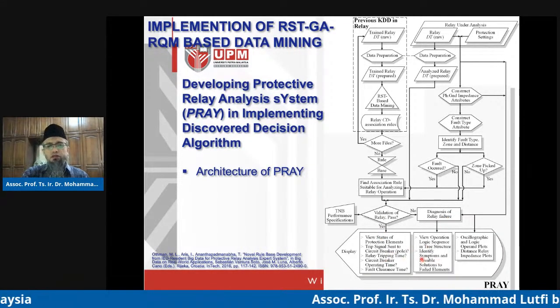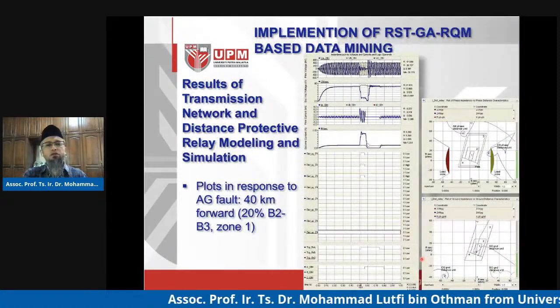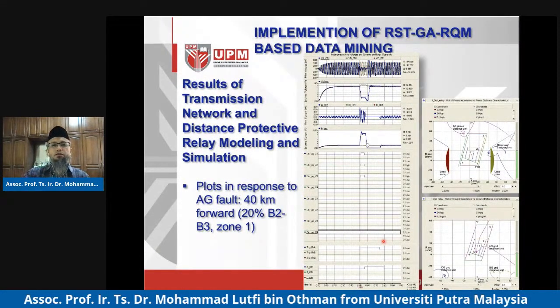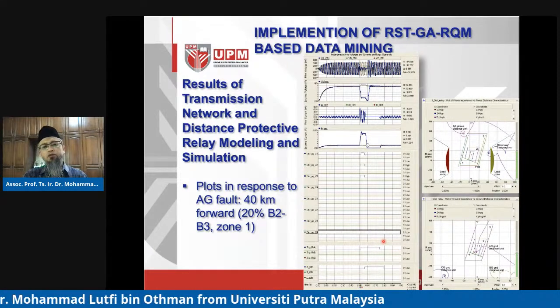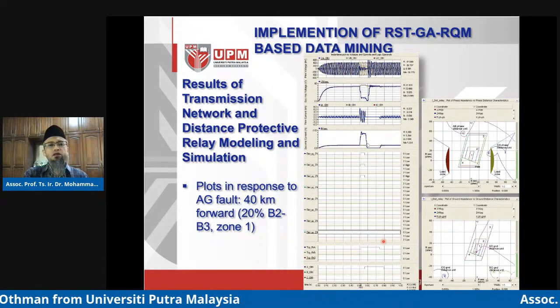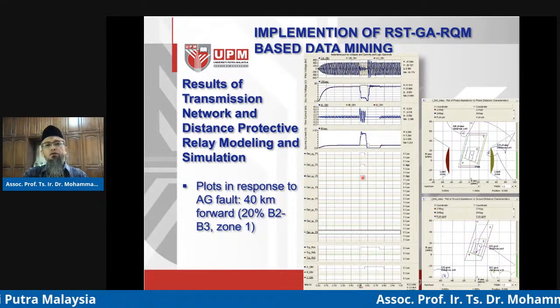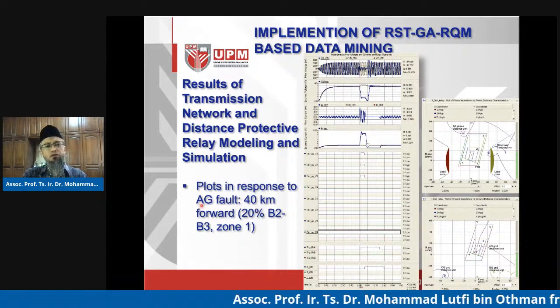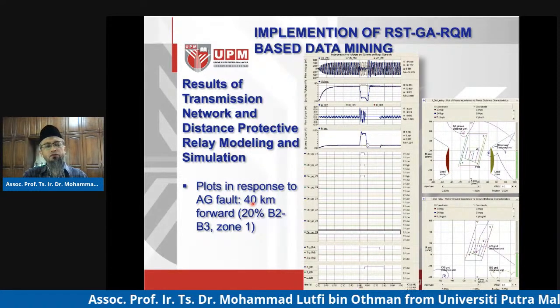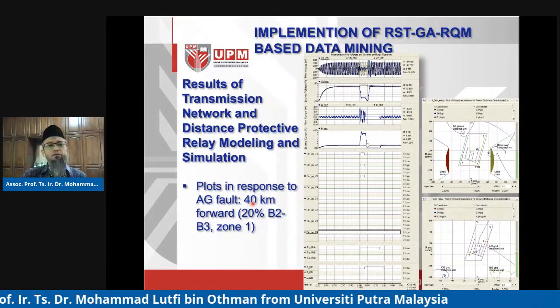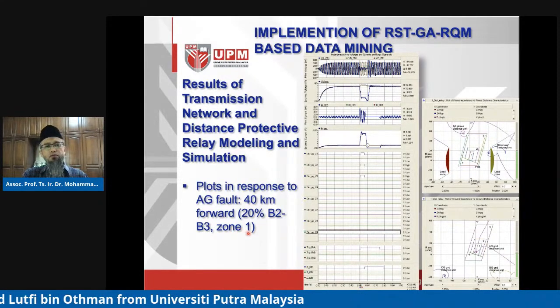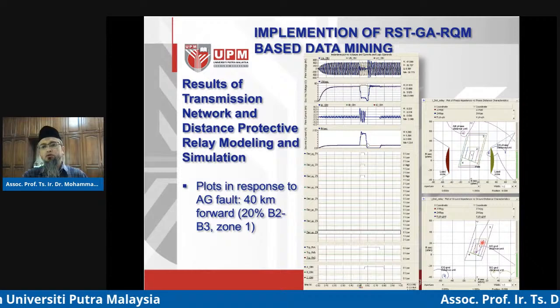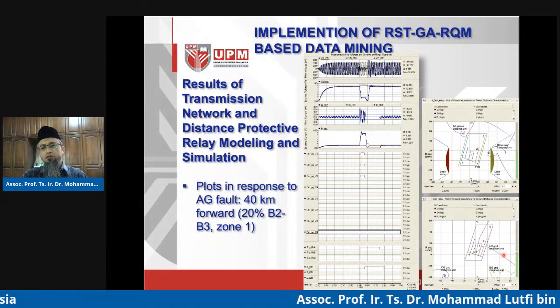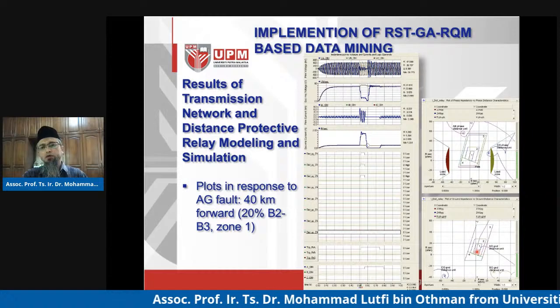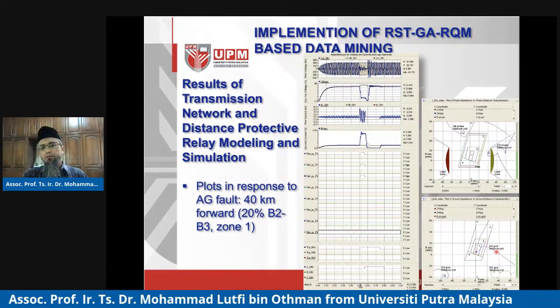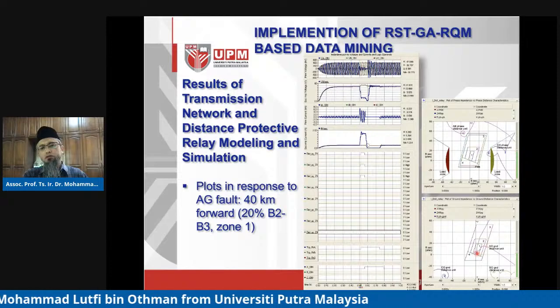So I'm going to show you later how the results are presented. This is the performance of the model relay in PSCAD of the Areva MiCOM P441 for a phase A to ground fault occurring 40 kilometers away in front of the relay. We call it zone 1, of course, because it's very close to the relay. You remember we're talking about zone 1, zone 2, zone 3. When there's a fault, the trajectory of the impedance would immediately go into zone 1. Of course, it would pass through the other zones to get to zone 1.